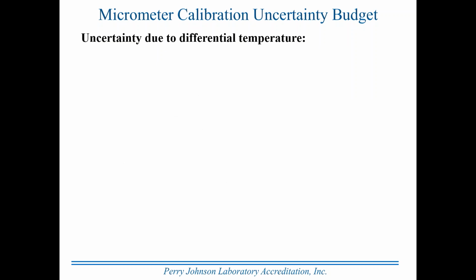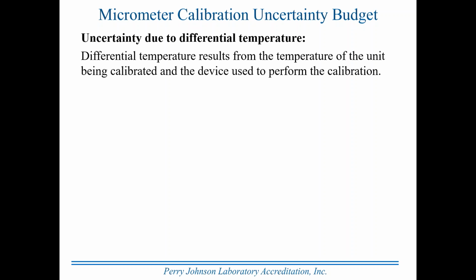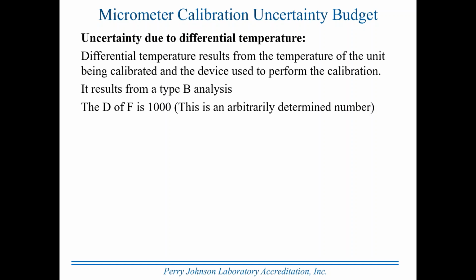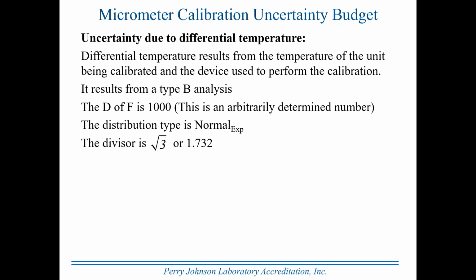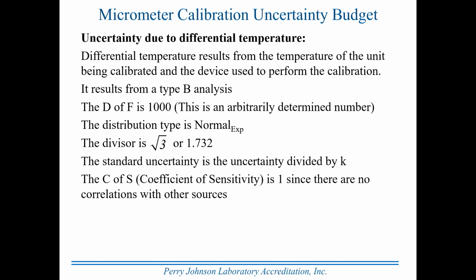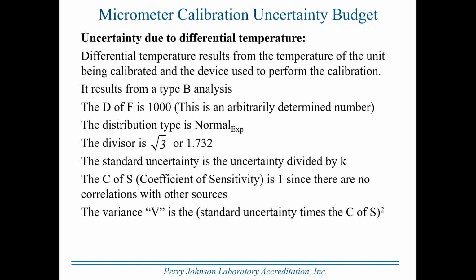Okay, this is the last contributor, uncertainty due to differential temperature. Results from the temperature of the unit being calibrated and the device used to perform the calibration. Type B analysis, degree of freedom is 1,000. Distribution type is normal expanded. Divisor is square root of 3. Standard uncertainty is the uncertainty divided by K. Coefficient of sensitivity is 1. Variance, again, calculated by the same method as expressed for the other 5.